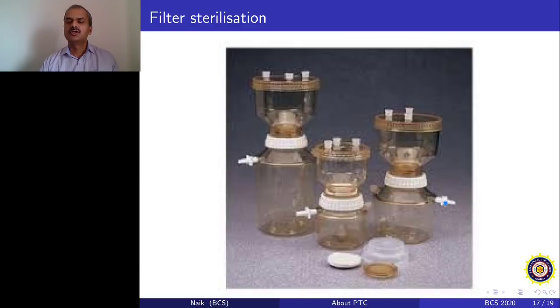Once you put on the vacuum pump, it will suck the air and pressure will build up at this place. Whatever solution is on top of the filtration assembly will get quickly filtered, and you will have the filtrate in the lower part of the filtration system. You can see this plastic structure is basically a filter assembly. These are the filters; the filter paper can be stored here and fixed over here. This ring sticks the upper assembly and the lower assembly together and fixes them, confirming the seal. Once the assembly is well tight, these knobs keep it airtight. This ring also keeps the entire structure tightly closed, and once you apply pressure on this side, you will have the solution in the filtrate.